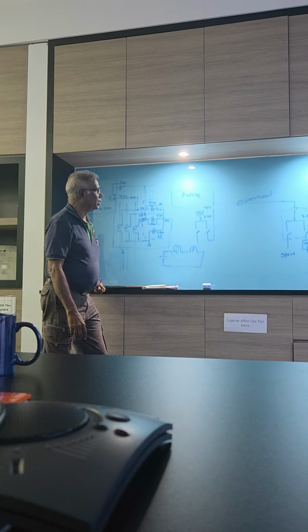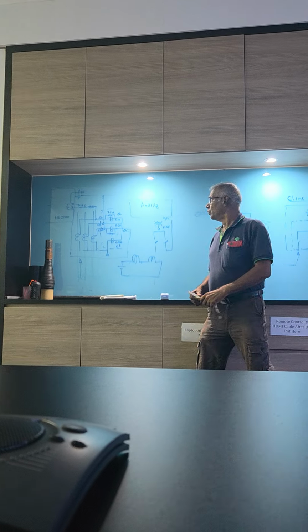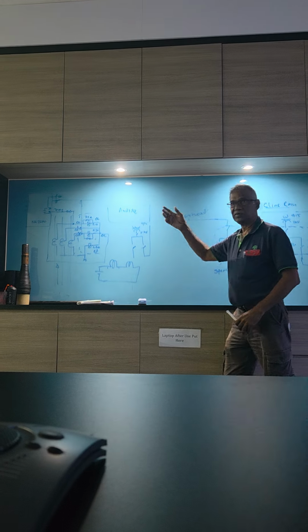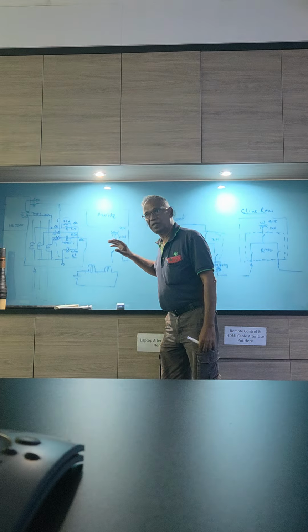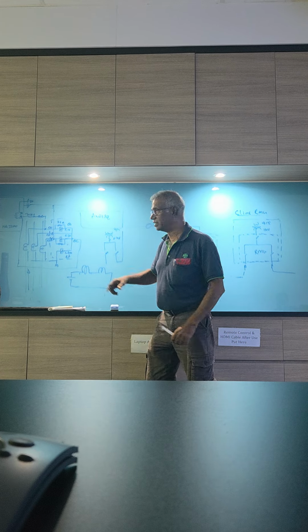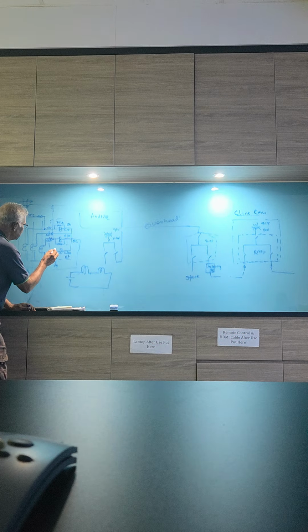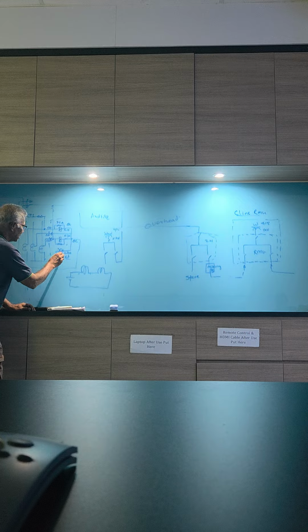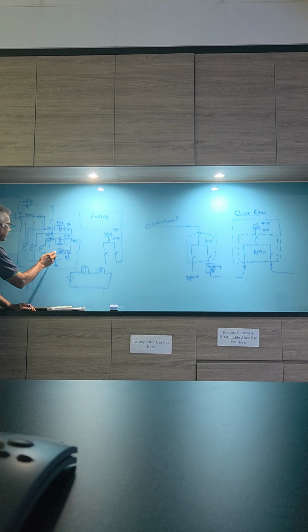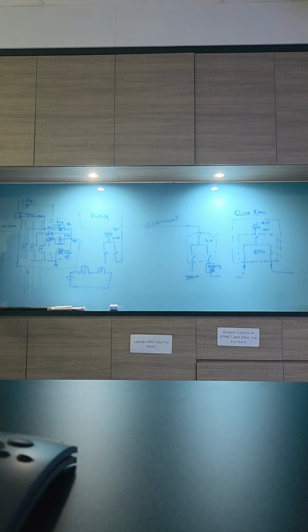So now what we can do, we have replaced. Then the final one, when we did the simulation, assume this is the relay that burned. So we went and replaced this new relay. But when we simulate, this relay didn't trip. It went and tripped this relay. So that means if there was a fault, that relay should have tripped, right? Yes, the question then, if there is a fault, this relay should have tripped. Nothing to do with the burnt relay, right? Nothing to do with the burnt relay.